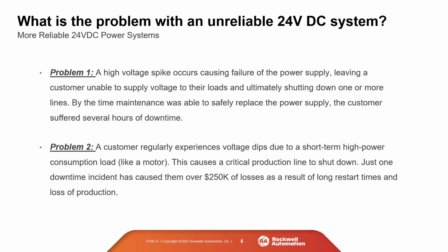So what is a problem when you have an unreliable DC system? Problem one, a high voltage spike occurs, causing a failure of a power supply. This leaves the customer unable to supply voltage to their loads, ultimately shutting down one or more lines. By the time maintenance was able to safely repair, the customer suffered several hours of downtime.